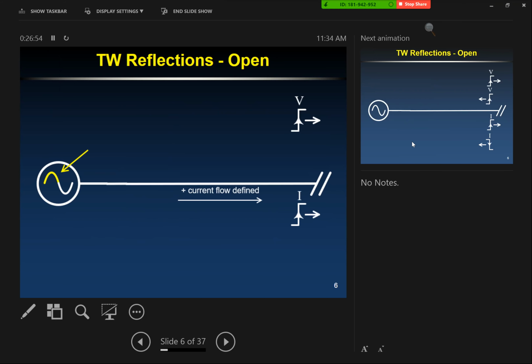This first example makes sense because we close the switch and energize the line. You get a positive voltage impulse traveling down the line, a positive voltage half cycle, and a positive current impulse because we're energizing the line, current flowing onto the line into that characteristic impedance of the line.